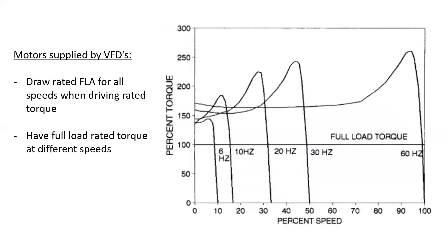Motors supplied by VFDs draw rated FLA for all speeds when driving rated torque. That means we could be running the motor at very low speed driving its full rated torque, or at three-quarter speed, or full speed — at each speed, the current drawn should be approximately equivalent to the motor nameplate FLA. Motors supplied by VFDs also have full load rated torque at different speeds, allowing very accurate control of torque delivery at every speed.